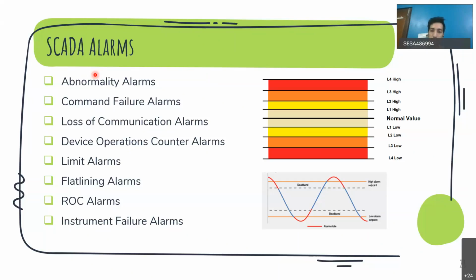Then command failure alarm. So an operator tried to operate one particular device. He tried to open or close a particular switch, but due to some reason, the command has failed. Since that is really important information, a command failure alarm will get generated to denote that. Similarly, loss of communication. When a substation communication is lost because of some issue in the communication equipment, an alarm gets generated. Similarly, for the number of times a device is operated, maybe due to maintenance purposes, you can only operate a switch 1000 times. So once that count is reaching 1000 or it has already crossed 1000, an alarm will get generated.